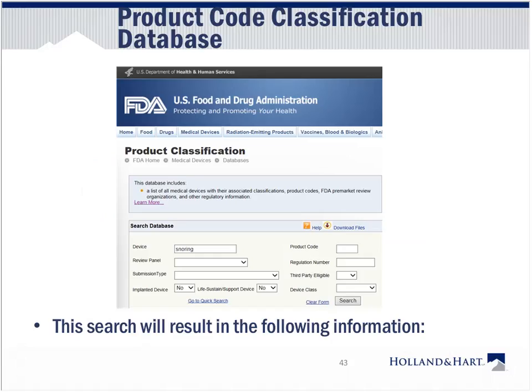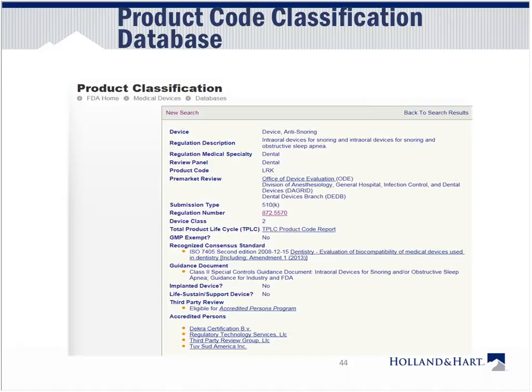So here you'll see that I've just taken a snapshot that shows that under the device we've put snoring, that it's not implanted, and that it's not life-sustaining. And when you put that in, you get the following, which is a wonderful piece of information. This is what you want to get to. So what we find out is that anti-snoring devices are regulated under 872.5570. That's a part of the code, and it gives you lots of information. It also tells you that it is not exempt. So these devices are not automatically exempt, which means that you're going to have to go through a pre-market notification process to bring this product to market.